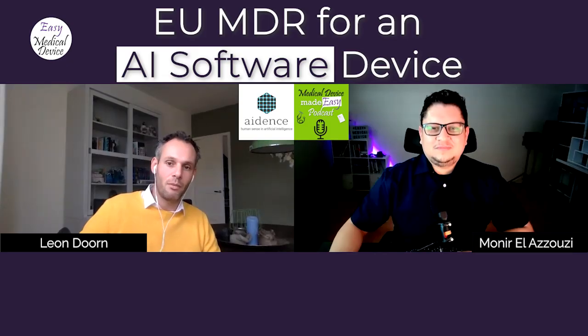But finally, now that we do have our MDR certificate, we still can't go to the market because of this discrepancy between the device that we have on the market, which is more up to date than the device that we submitted back then to our notified body.